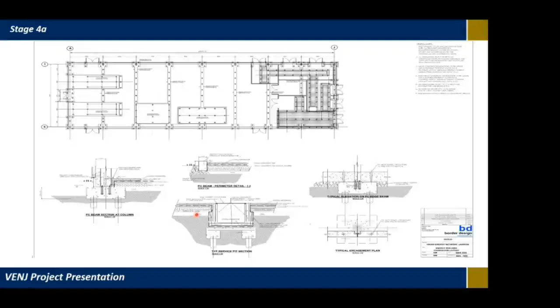In terms of the actual energy centre itself, these are more detailed drawings showing what we've got inside, including the heat pump installed here. Because it's an ammonia heat pump, there are further challenges: it uses ammonia, so if there's a leak, it has to be vented. There's a vent line that runs from the heat pump enclosure up to the chimney, so any emergency discharge will dissipate up there.